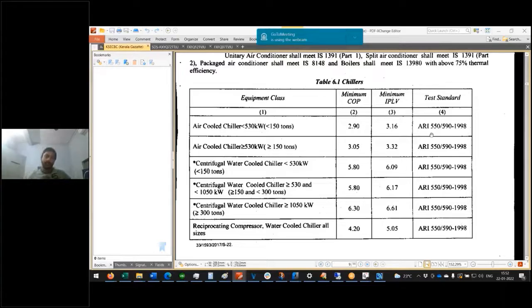The COP at design conditions, by design conditions I mean for a location like Kerala, would probably be less than what is defined over here. Because the test standard considers the outdoor air, I think, at 35 degrees Celsius or so, but in reality, your design condition will probably be 40 or maybe 42. So please remember, when you're asking for a test certificate or COP, or even when you are vetting a tender document, please make sure it is written that the COP is at ARI test conditions and not design conditions.